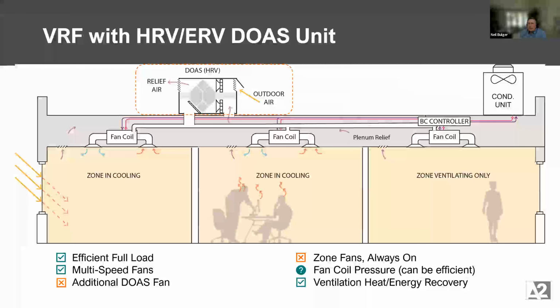the size of the coil and then its performance in the software, from my experience, if it's 20% larger, I have not seen strong differences in how that fan coil performs. In reality, you have to buy a larger fan coil. It's 20% more. So oftentimes whether or not to downsize has become a cost question. How do we really rely on the HRV? Do we have faith that it's going to work? What are we using? So I've seen it more impactful on the architecture and the engineering of the system to get it installed and less so on the software giving wildly different answers. If it's plumbed in the software the right way, you should get similar answers.